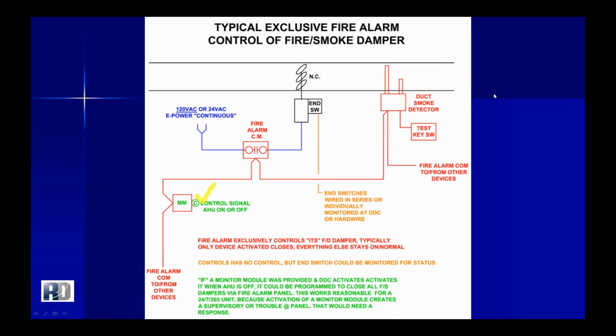This is similar to what Dave had talked about before with having a building that's monitored 24/7. If the fire alarm is performing a function, it has to come with one of three things: a supervisory, a fire alarm, or a trouble. And anything that the fire alarm produces needs to be acknowledged. So if you are in a building that has an occupancy schedule, so it's off at night, and your fire alarm is doing the work, then every single morning when you come in, you'll be going to your fire alarm panel and clearing your supervisory. So typically you don't see this method utilized in buildings with schedules that are not monitored. Similarly, the end switches, though they don't have any control aspect to them, can be monitored. So you can still utilize your end switches from a control perspective so that you can monitor the status of your dampers.